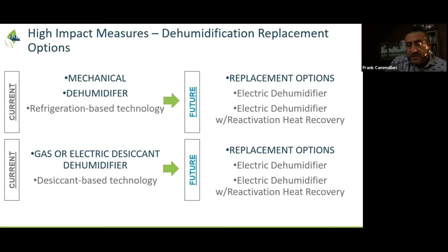That basically is being able to recover the heat that exits the exhaust to use somewhere else. Basically, the desiccant needs to be heated to make the thermal wheel a lot more effective at reducing the humidity, and that usually produces a higher exhaust air temperature, which can be recovered to provide heating somewhere else in the facility. So when you're considering replacement options, electric should be top of mind. And if there's an opportunity, you can put a waste heat recovery coil before the air is exhausted out, so you can use that somewhere within the facility.